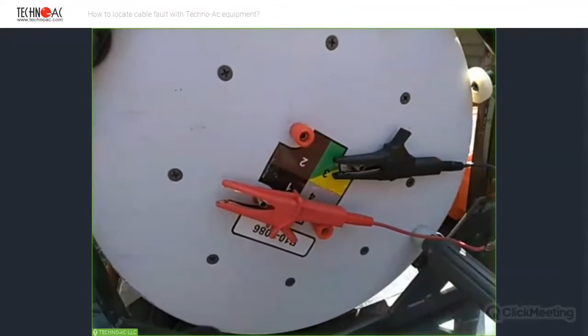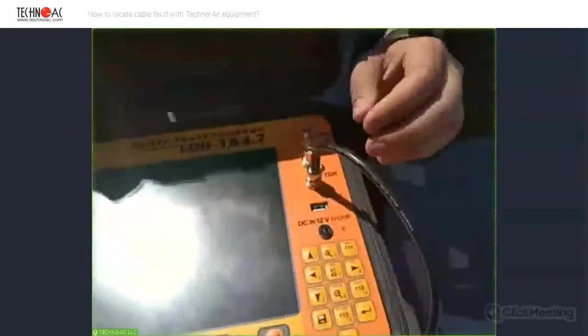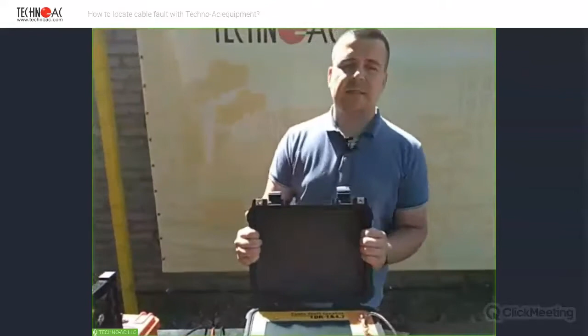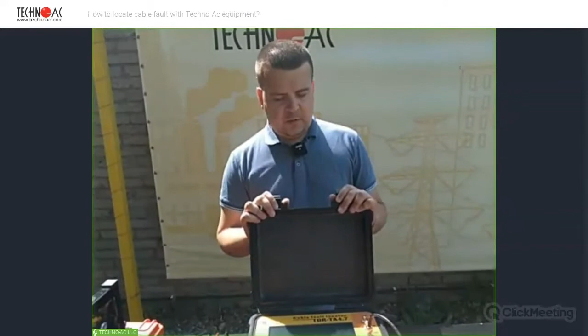We're connecting the crocodile clamp to our cable, and we have also connected the other end of the wire to a TDR connection port. So how does TDR work? TDR sends a low voltage pulse inside the cable, and if there is damage in the cable, this pulse is reflected and sent back to the TDR. Then the device evaluates the time, distance and speed of the return pulse, and that is how you can calculate at which distance you have your fault, what kind of fault it is, and what the overall length of the cable is. So let us start the measurement and we will see together what the device indicates.